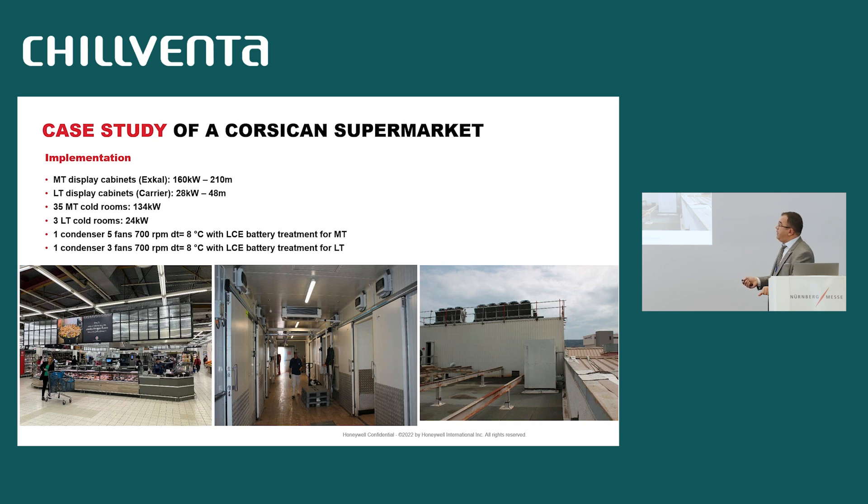Other photos show the implementation of this solution. We installed 210 linear meters of display cabinets for medium temperature with an Exkal solution, and 48 meters of display cabinets from Carrier for low temperature. In total, we have 35 cold rooms totaling 134 kilowatts of cooling capacity, and 3 cold rooms for low temperature for a total of 24 kilowatts. You can also see the condensers — two condensers, one for medium temperature with five fans and one for low temperature with three fans.